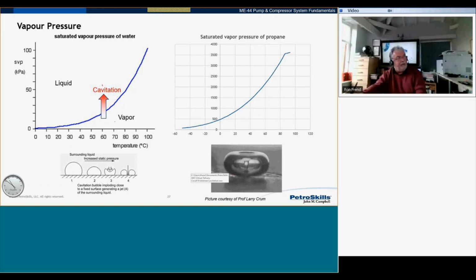This is a photograph I was given by a very nice gentleman. Last time I talked to him, he was a professor in Alaska. And this is an ultrasonic image of a cavitation bubble. And you can see the jet inside as the bubble's collapsing. And these can cause huge pressures, and it will end up causing fatigue erosion on the surface of the material, either on the pump or even on the impeller itself, or even in other parts.